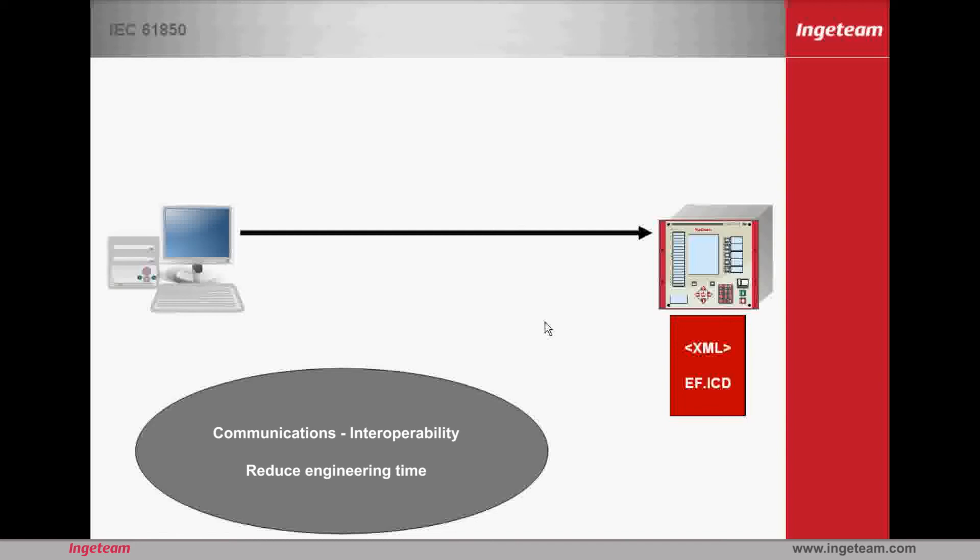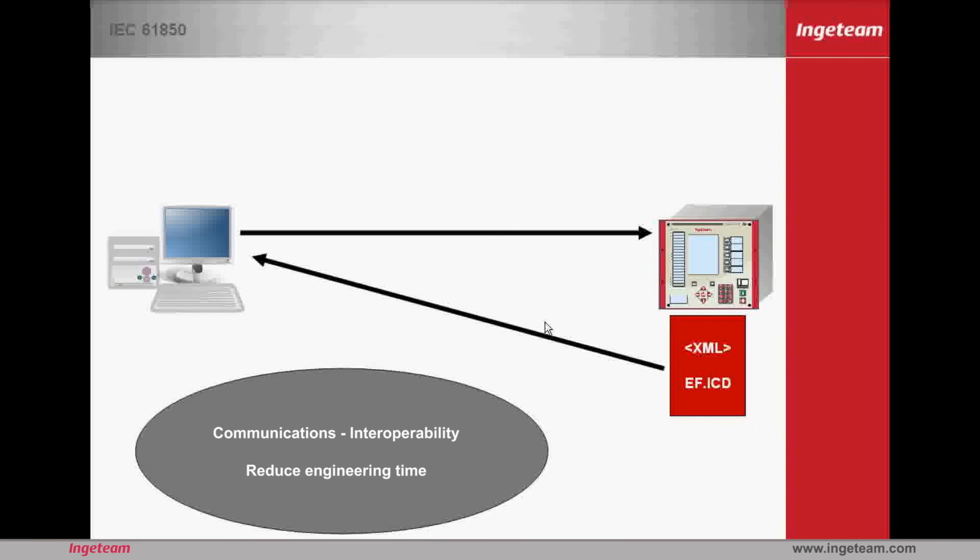Furthermore, and highly helpful during the configuration of communications, every IEC 61850 device is associated with an XML file containing its information model and its capacity and communication behavior towards the client. Hence, the classic communications profiles indispensable in other communication protocols are designed and expressed in IEC 61850 in the configuration XML of the device itself. The XML that accompanies the device or which is generated for the device using an engineering tool can be imported by the communications client device. Hence, using minimal manual intervention, the two devices, client and server, are configured. Consequently, the client knows the server's capability perfectly, and with very little effort, high-level communications are obtained with excellent performance and great flexibility.